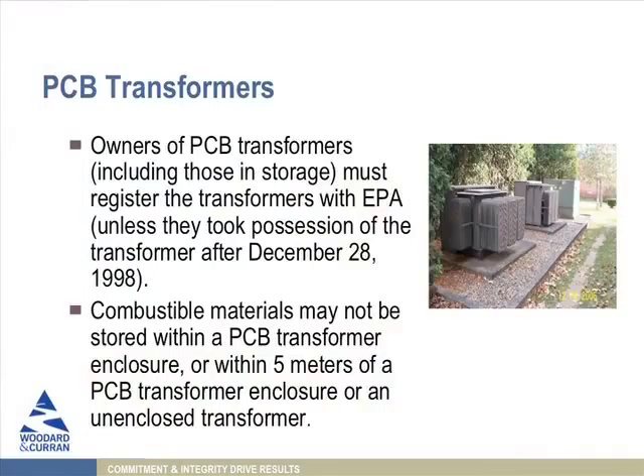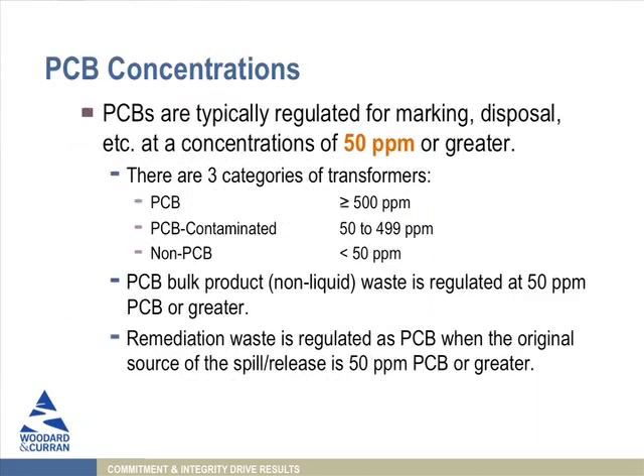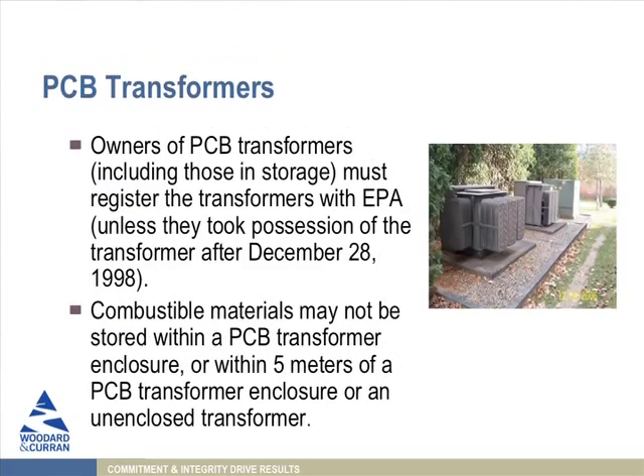Now we're going to shift over for a moment and talk about transformers. When we talk about PCB transformers, remember this is a specific term the regulations use. A PCB transformer means 500 parts per million or greater. Straight PCBs refers to 500 parts per million. If something is PCB contaminated, that's between 50 and 499 parts per million. This is a term of art the regulations use, distinguishing between different categories of items. So when we talk about PCB transformers, or later PCB capacitors, we mean equipment with 500 parts per million contamination.